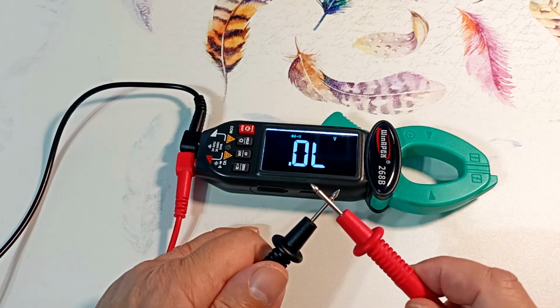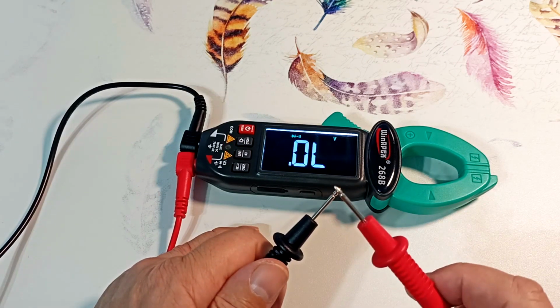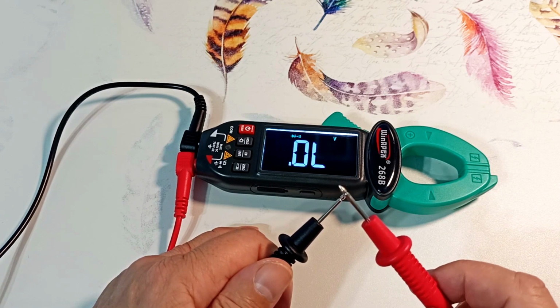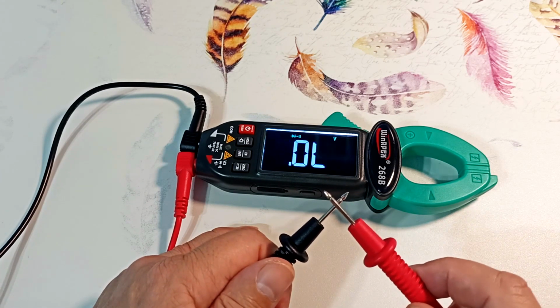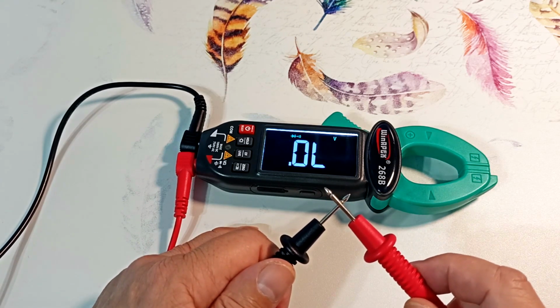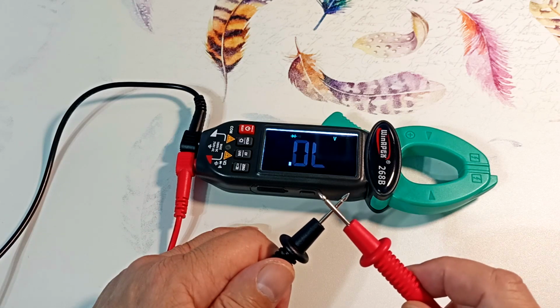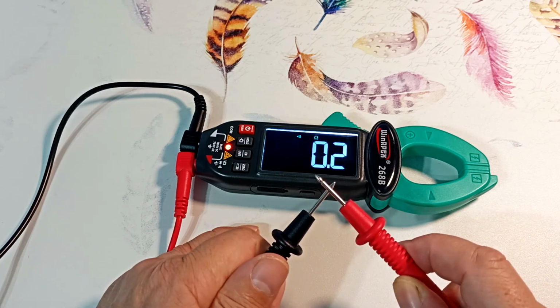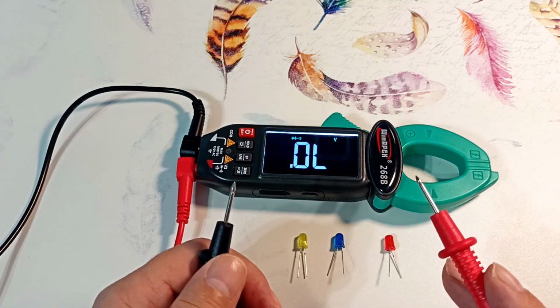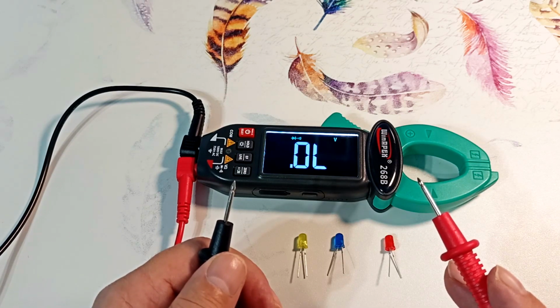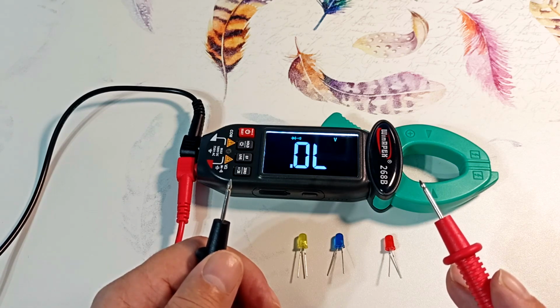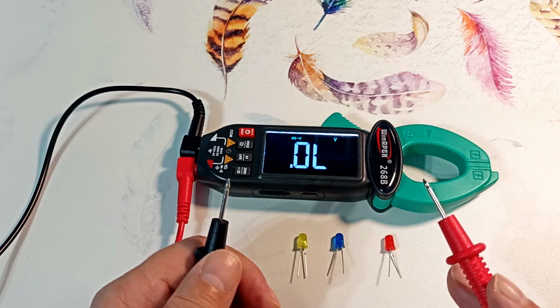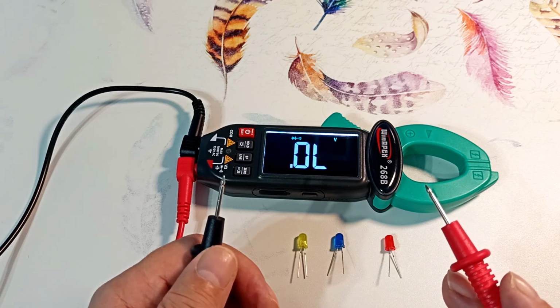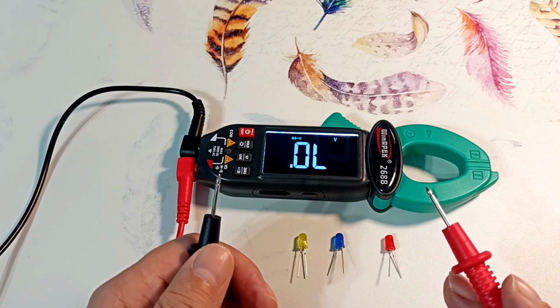In the dialing mode, a signal sounds when the resistance between the probes is less than 50 ohms. As you can see, it measures latency. Wait a while for the device to respond. When testing diodes, voltages up to 3 volt and currents up to 1 milliamp are used, which allows you to test almost any LED. At the same time, the voltage at the PN junction is shown.